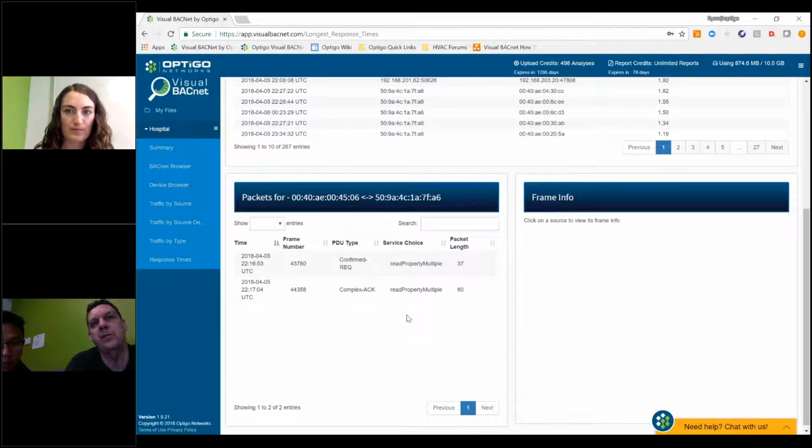So when your customers, and they're all out there, complain that the graphics are slow, take a look into this one. Because if you have a graphics refresh of 5 to 10 seconds, plus the 11 seconds to actually get the data, you can be 20 plus seconds before that data refreshes. Wow. Yeah. But this is an easy one because you know the 2 controllers that are in play, and you can look on your map to see what the route is between them and start narrowing it down.